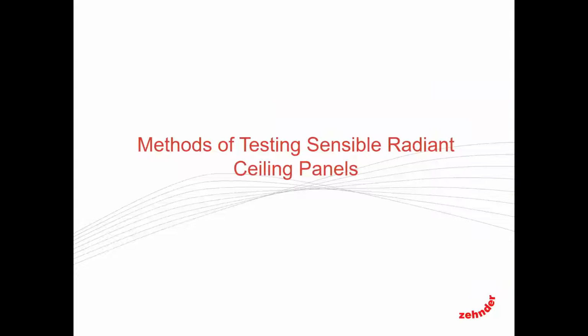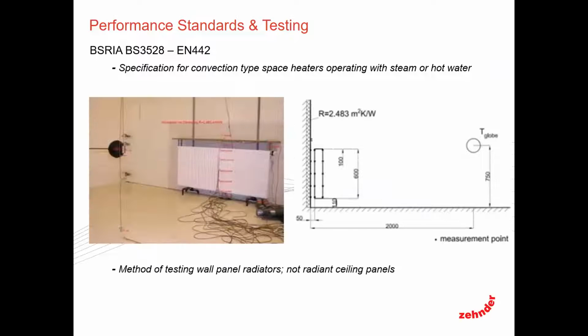All right, so we've talked a little bit about the performance. It's important that we now talk about how panels are tested. About 35 years ago globally, when the industry really started, there was no standard of testing. So our industry, again globally, looked at and said, what's the closest thing out there that we can utilize to test a radiant ceiling panel? Well, there were wall panel radiators on the market. And there was already a standard developed for these wall panel radiators, which was 3528, the first one. It's now called EN442.